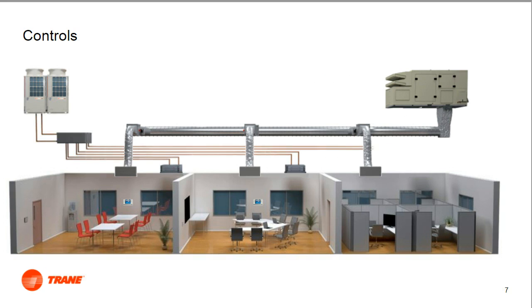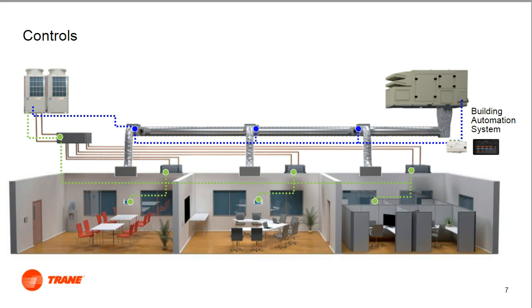Each piece of refrigeration equipment has its own factory-provided unit controller. The VRF equipment operation is coordinated by interconnecting their unit controllers on a proprietary network. The outdoor unit controller directs the VRF system operation. The ventilation system has its own unit controller and typically operates only during occupied hours. Control coordination between the VRF and ventilation system can be handled a variety of ways, from standalone operation to a building automated control system. The focus of this program is to discuss each of these subsystems and their various options.